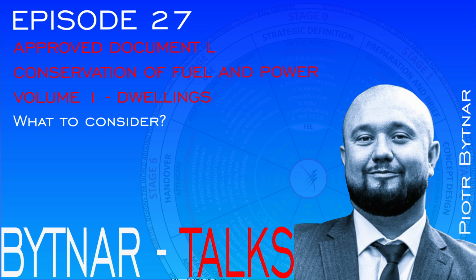Now off to micro combined heat and power, called micro CHPs. It is important to ensure the micro CHP heating emission rate is not greater than that of a regular boiler using the same fuel as the CHP. The emission rate should be established using the DEFRA method or to evaluate the annual energy performance of micro-generation heating systems in dwellings, BRE PAS 67, together with the plant size ratio for the temperature difference of 24.2 centigrade, measured heat output over heat loss of the building.